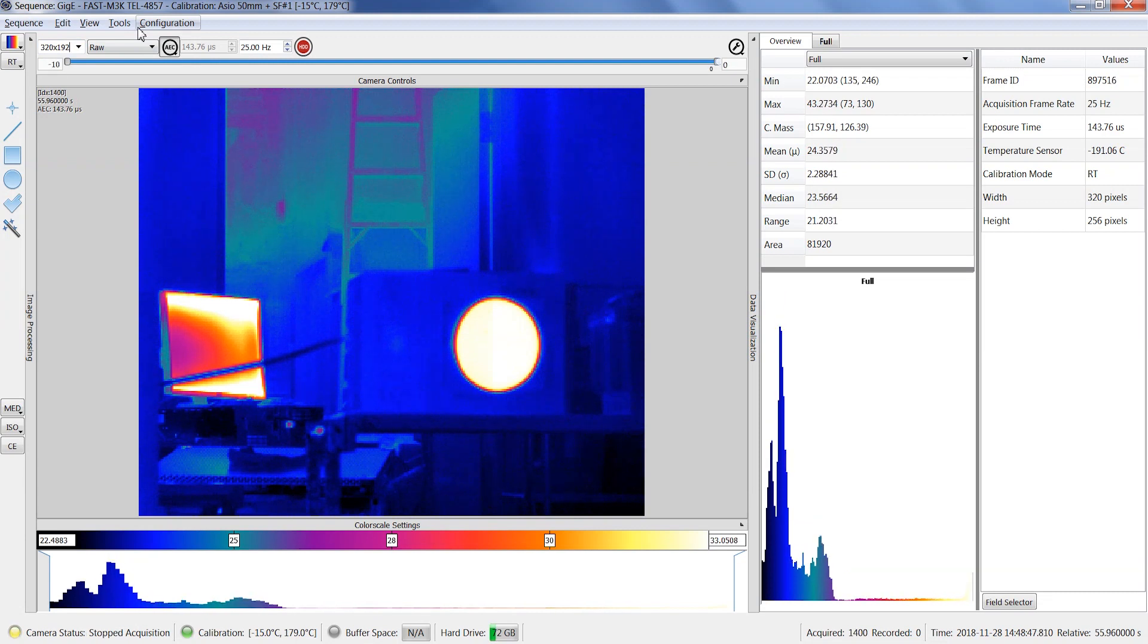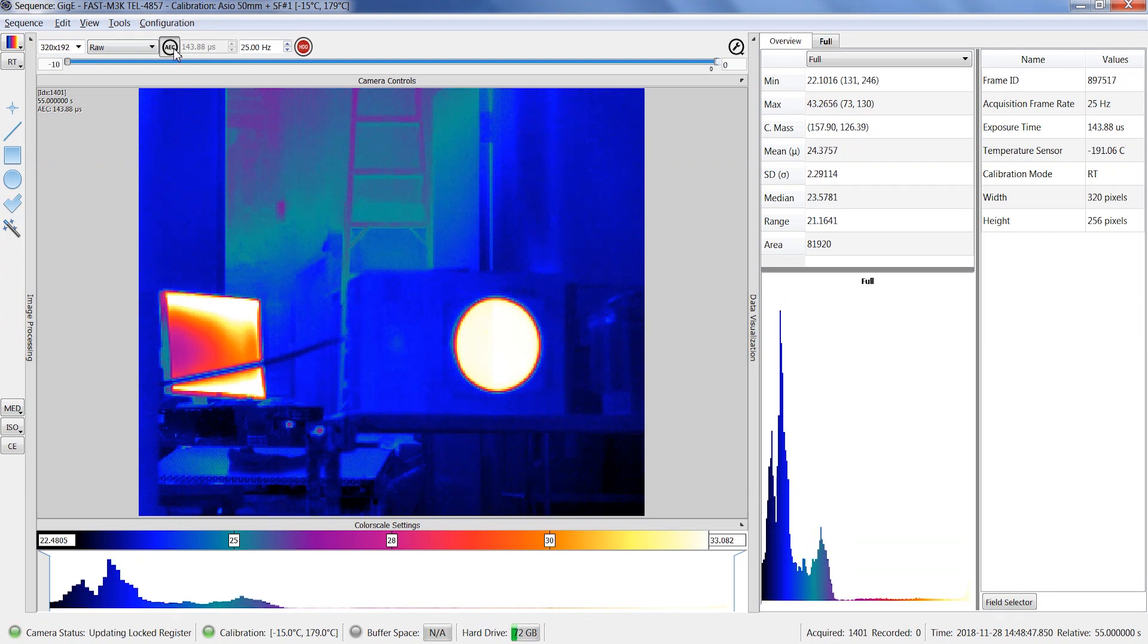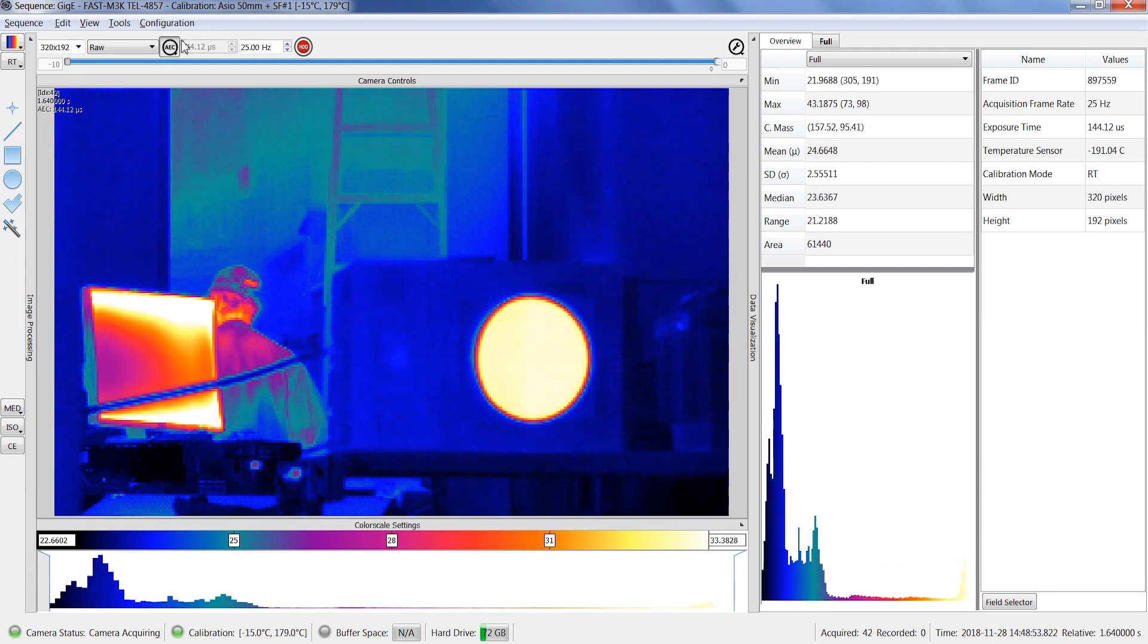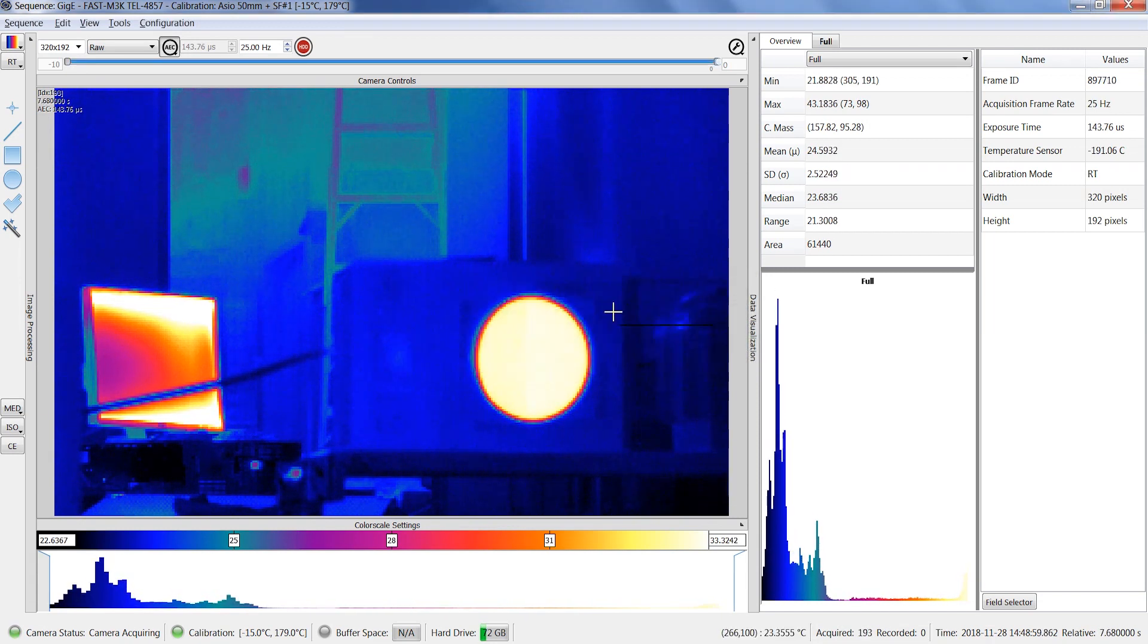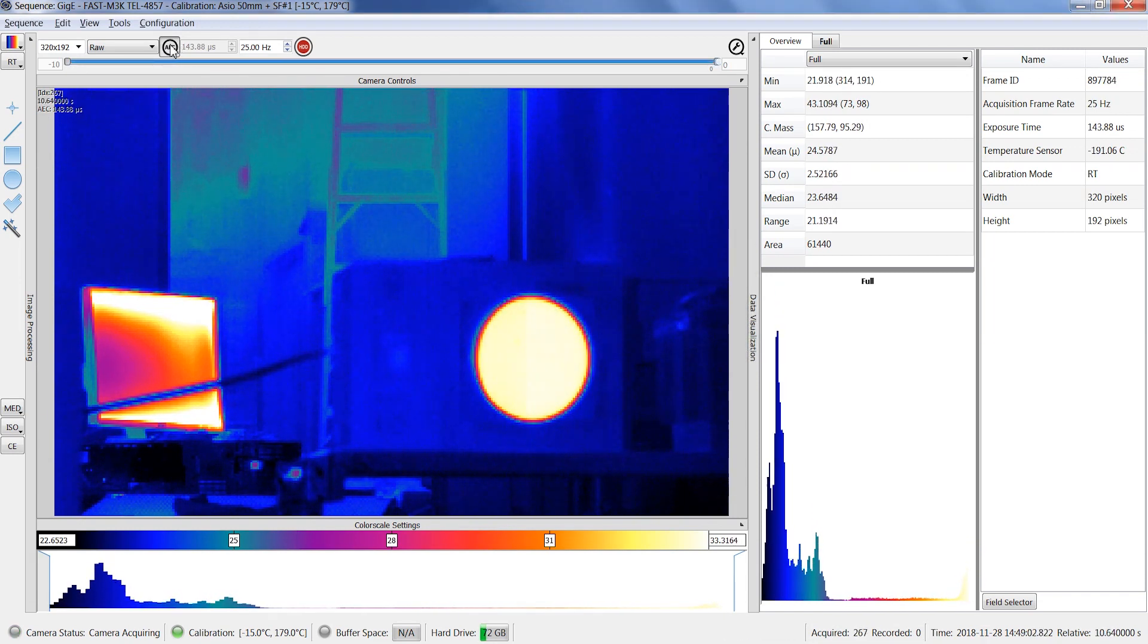The exposure time can be used either in fixed mode or by using the automatic exposure control, which is a feature unique to Telops thanks to our permanent calibration. If you disable the AEC mode, you can manually set the exposure time. Refer to the tooltip if needed.